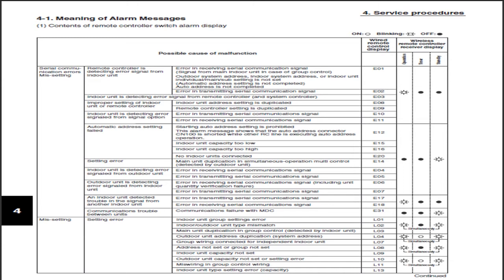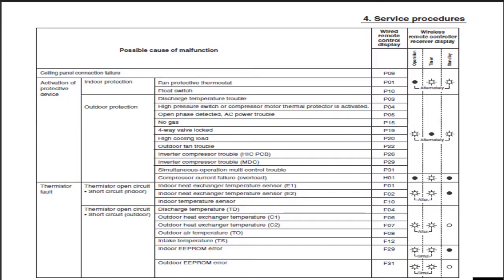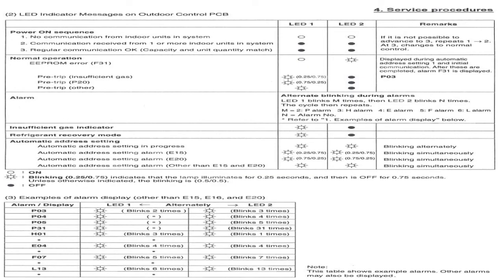Displayed on this first slide are the E and L type alarms. This second slide shows the P, H, and F type error codes. As seen from this chart, these types of error codes would be due to a problem either within the indoor or outdoor unit, depending on the error code being displayed. This slide is an illustration of how the error codes would be interpreted from the outdoor unit's main control board.